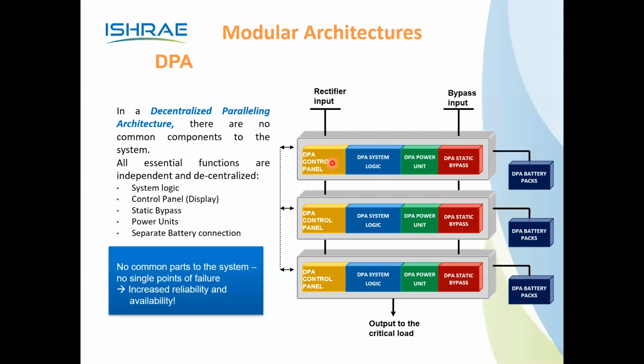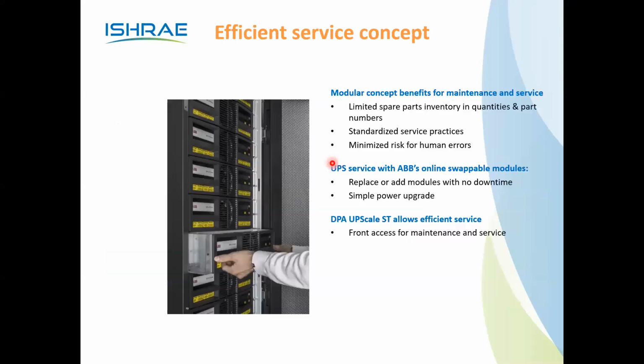This is called a decentralized parallel architecture. This is a multi-master configuration, not a master-slave configuration. So a limited spare parts inventory is needed, just one module they can keep, depending on their UPS capacity, for the service support. They can just swap it. Here you can see each module has the controller, display, and everything. Just hot swapping, no need of shutdown. Right?